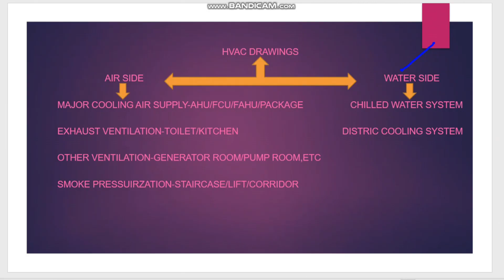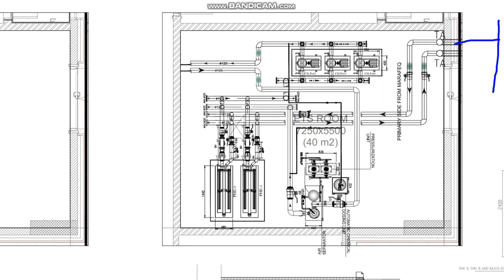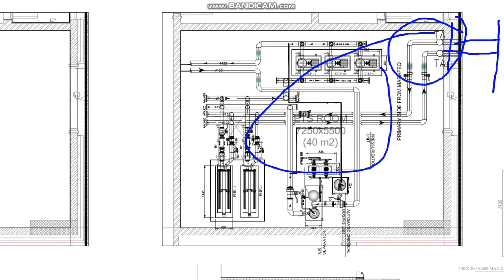In the part 1 video, I explained the hot tapping connection from the outside. After the hot tapping connection, the supply and return line coming from outside to inside the ETS room, when the pipeline enters the inside line, we have to provide an additional accessory called a puddle flange in the wall. Let's see the details of the puddle flange.